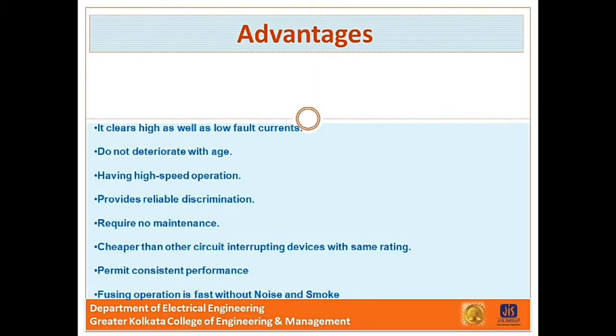Next one, what are the advantages of using HRC fuse? Now, first advantage is they are capable of clearing high as well as low fault current. They do not deteriorate with age. They have high speed of operation. They provide reliable discrimination. They require no maintenance. And they are cheaper than other circuit interrupting devices of equal breaking capacity. Next one, they permit consistent performance. And the last one, fusing operation is fast without noise and smoke. So these are the advantages of using HRC fuse.